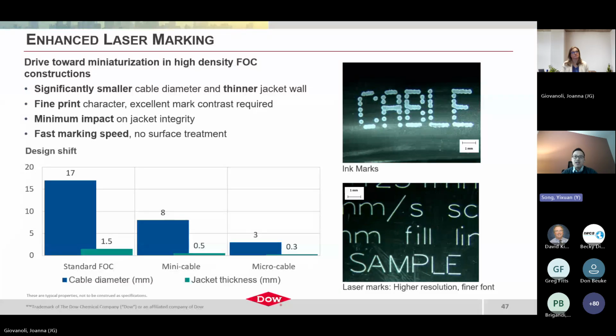But there's a catch - conventional black jackets cannot be laser printed because the full carbon black content dissipates the laser energy too fast. So we formulated specialty jacketing compounds, including 6221, with a wide range of product offerings from low density to high density. These compounds not only provide laser printability but also guarantee comparable outdoor UV resistance compared with conventional black jackets.